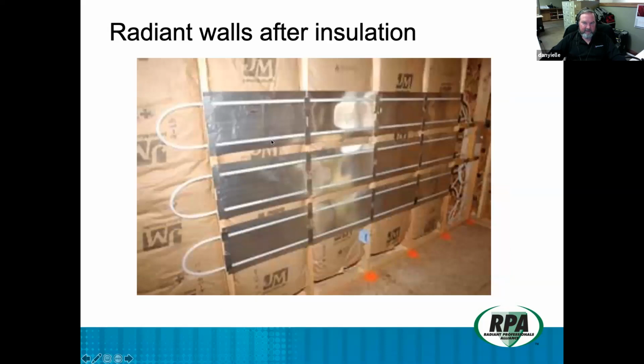And we used non-electric thermostatic radiator valves to be able to control the flow of hot water through this. So we have a modulating boiler, we have a modulating pump, and we have modulating heat controls. This is like the ultimate heating system. It only uses what it needs to be able to provide the comfort and maintain decent conditions within the space.